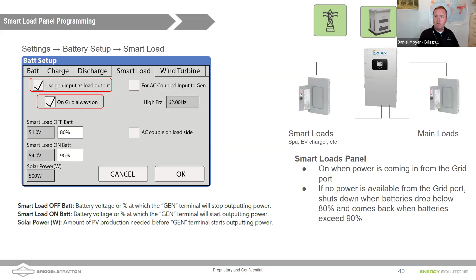But look down on the left here. Smart load off battery, that means when the batteries are below 80%, that smart load port is off. Smart load on bat, that means when the batteries are 90% or more full, getting full, we'll turn that smart load port on, or the gen port essentially. And we have a little differential in there, right, because we don't want them coming off and on, flipping and flopping back and forth.